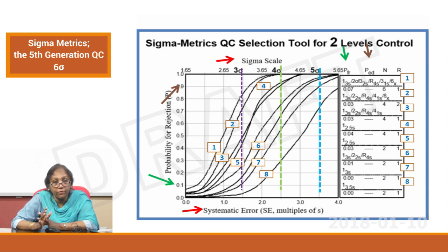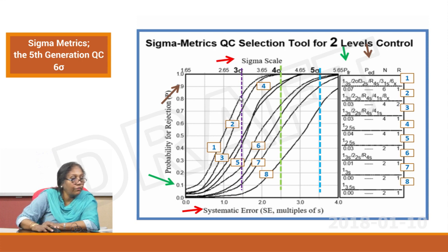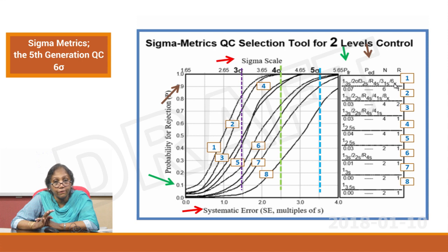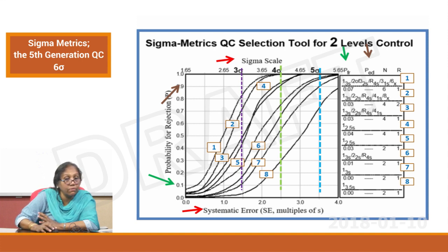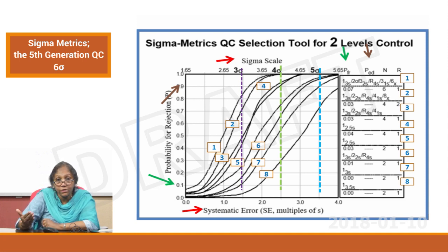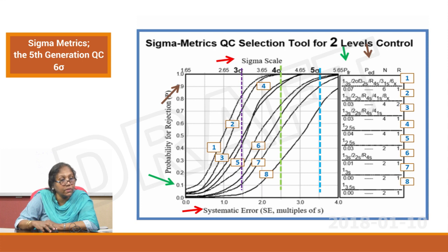For a 3 sigma performance, the best error detection is about 82 percent. For that 82 percent I have to follow rule set number 1, which means I have to follow 1-3S, 2-of-3-2S, R-4S, 3-1S, and 6X — all these rules will have to be followed for that analyte to remain under control. That is a lot of rules, and you have to do an N of 6 with an R of 1. Because to have a 6X rule, you need 6 measurements at one go — unless you have 6 readings when you review at 10 o'clock to decide whether to accept or reject the run, you cannot follow a 6X rule.